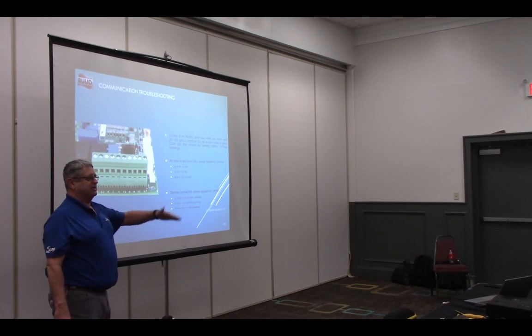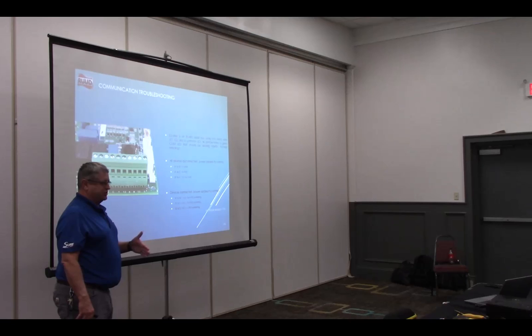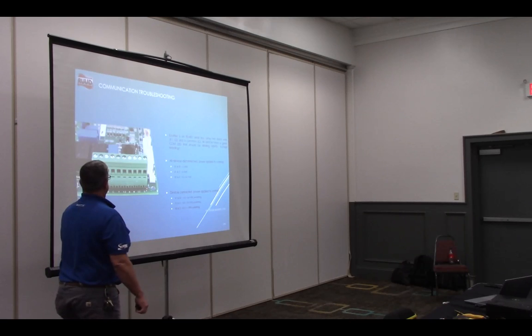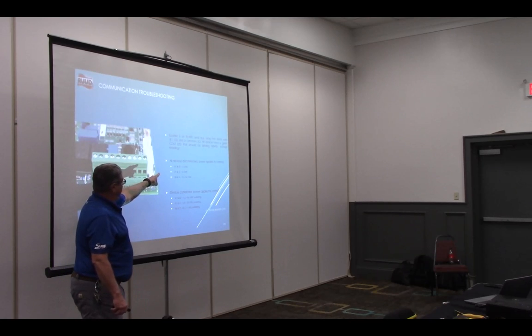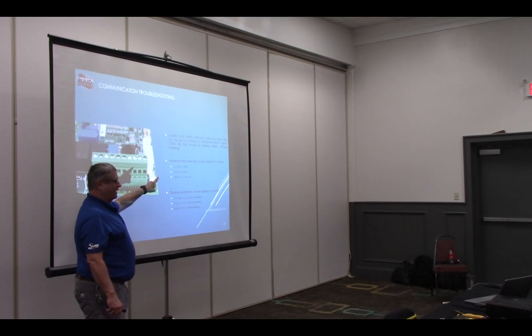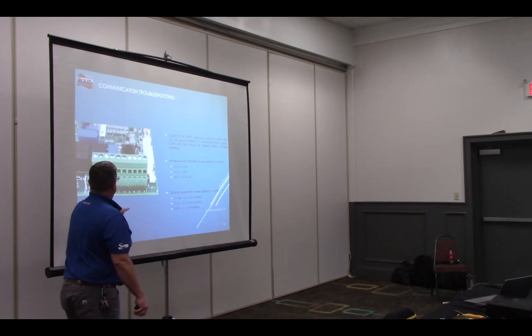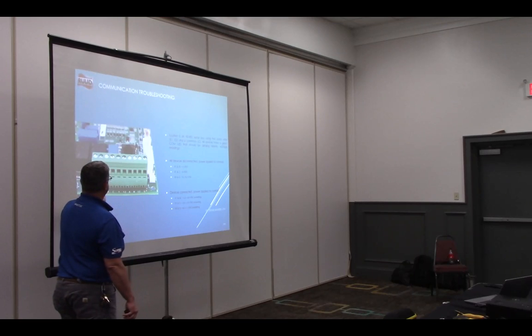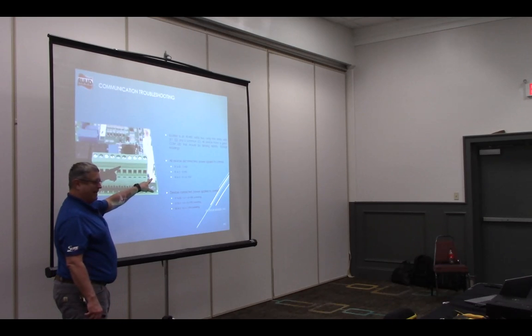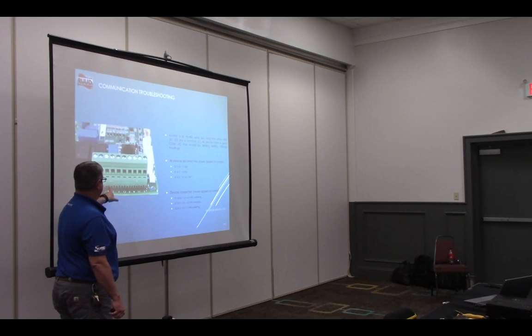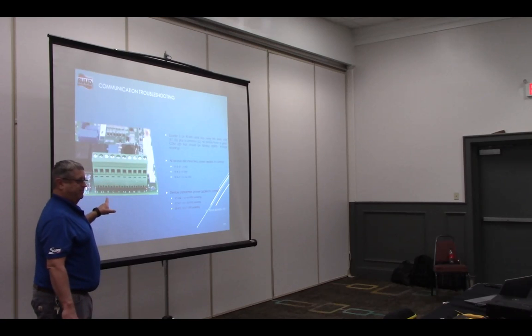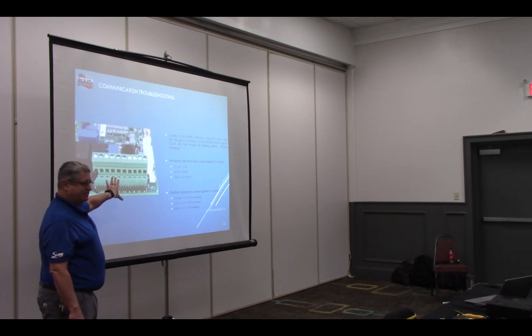Let's say we have an outdoor communication error, okay? It says here, all devices disconnected, power applied to control. We're going to start on the outdoor board. So that means all devices disconnected. We're going to disconnect E1 and E2, power applied to control. So we need to leave R and C powered up, okay? Because we need power applied to it.